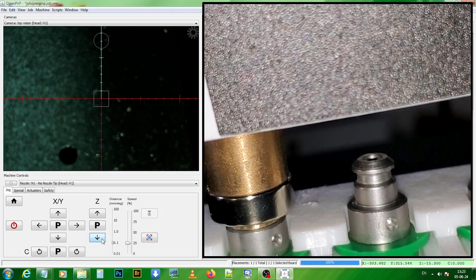Now we need to update some fields. We are in the third position. I acquire the position of the nozzle clicking on this icon. Apply. The X value for the third position is the right value for all the positions, so I copy it and paste it in the other positions. The Z value for the first and second position is the right one to avoid the tip already loaded in the other nozzle crashing the holder.